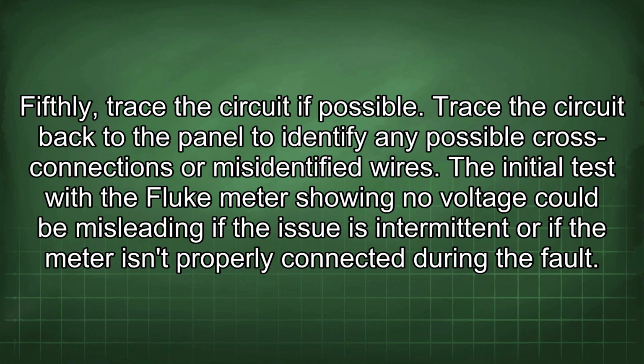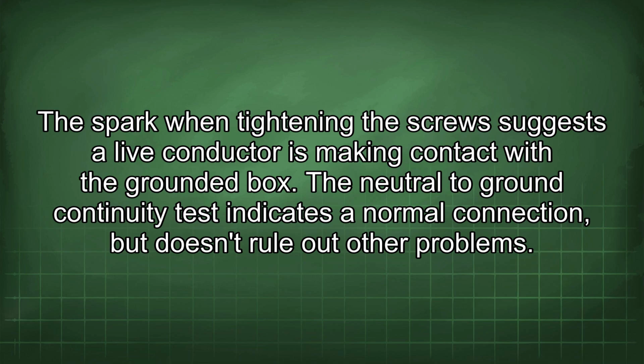The initial test with the Fluke meter showing no voltage could be misleading if the issue is intermittent or if the meter isn't properly connected during the fault. The spark when tightening the screw suggests a live conductor is making contact with the grounded box. The neutral to ground continuity test indicates a normal connection, but doesn't rule out other problems.